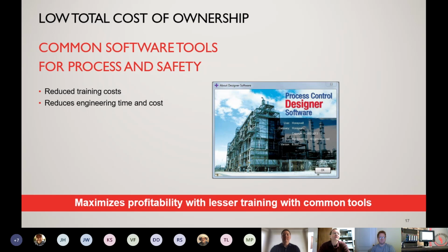What Honeywell did a long time ago when they came out with this product is they took a look at a lot of typical applications out in the field and put together a set of library function blocks that, with a quick drag and drop onto the screen, accommodate a lot of different applications where you don't have to create your own function blocks. For example, there are standard function blocks for dew point, relative humidity, position proportional control, if you still have some of those out there, and carbon control for heat treat applications.